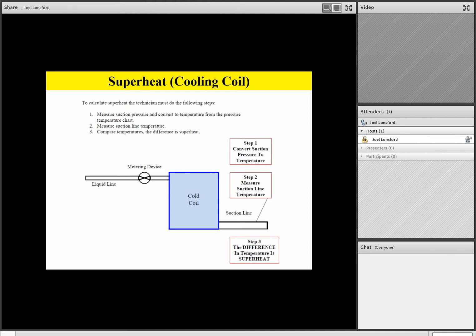Now remember, team, there's only 3 conditions the cold coil can ever be in. It can be flooded, there's too much refrigerant in there. It could be starved, there's not enough refrigerant in there to get the job done, or it could be normal. Now please write this down, or make a note of this. Normal superheat on the cold coil on a heat pump should be about 10 to 15 degrees Fahrenheit superheat in the cooling mode. One more time, normal superheat on the cold coil in the cooling mode of operation should be about 10 to 15 degrees of superheat.